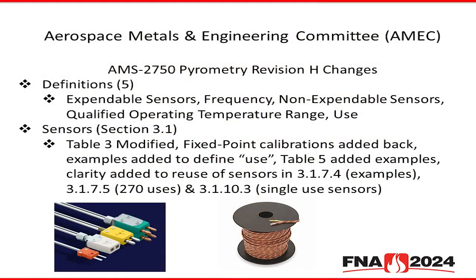When we took fixed point calibration out, a lot of the European suppliers, thermocouple people, said, hey, we use fixed point calibrations. You're putting a real crimp on us. So we said, all right, we'll put that back in, but we still have that 250-degree rule between calibration points. Table 5, we added more examples for clarity. If you've looked at the documents side by side, you'll see a lot more examples and things that we've added to help clarify things for you guys.